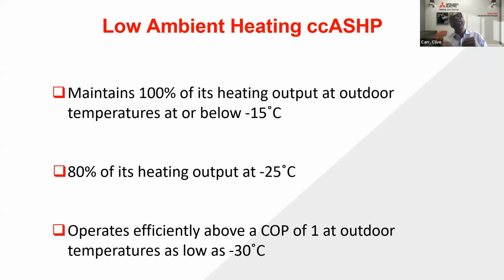So in Canada, we look at these two points to see our heating output, the efficiencies, and the operating range. A cold climate heat pump must be able to maintain its heating capacity at the higher temperatures, 47 degrees Fahrenheit and 17 degrees Fahrenheit. It should be able to maintain that heating capacity at temperatures as low as minus 15 or lower. We're at the point where we're maintaining that heating capacity down to temperatures as low as minus 20. And we continue to work to improve that, where we can offer 100% capacity down to minus 25, therefore improving air source heat pump technology's applicability as the primary and only heating system.